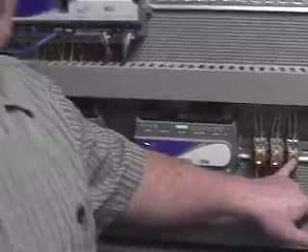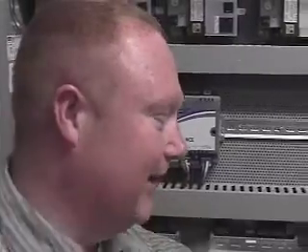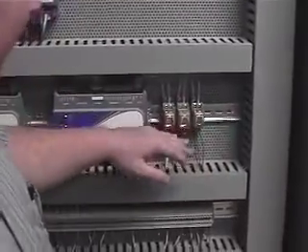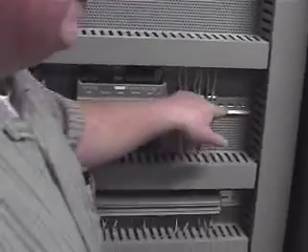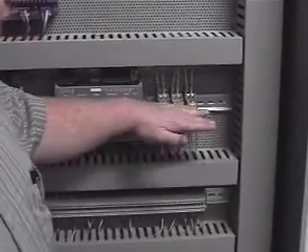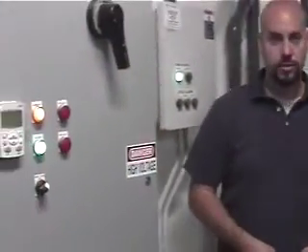We were waiting for the sensor to mount that came in, so it's kind of a change to add that later. But anyways, on the air handlers, you always want these to be lit. If something's not lit, this is a hardwired safety that goes to the drive. When that red light's not on, that's your safety relay. So all these are run in series. If any one of these trips out, that light will go off and the drive won't run. On the freezestat, they said 35, between 35 and 37. I believe it's 35. Yep, safety circuit.